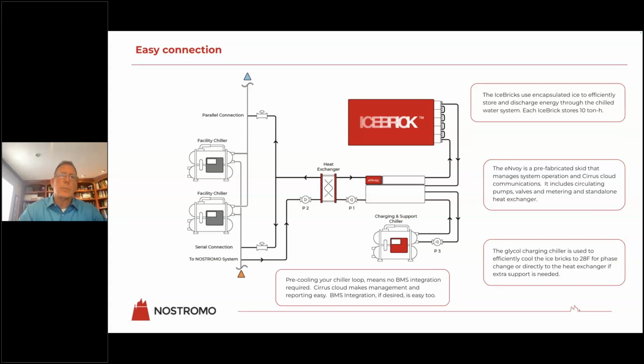Schematically, it's pretty simple. The IceBricks at the top can be added or subtracted depending on the capacity needed, usually designed up front. If the building expands later or needs to contract, you can either abandon existing ice bricks and shrink the system size, or add more ice bricks to expand it. At the bottom is an example of a charging chiller and the heat exchanger, and everything to the left is the existing chilled water system.